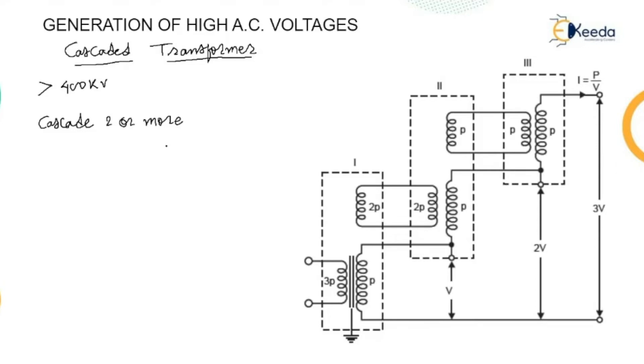The transportation cost and erection cost can be reduced, making transportation and erection easier. The transformer cost can also be reduced. Heavy insulation is required in a single-stage transformer for high voltages exceeding 345 kilovolt. It is found that the cost of insulation for such voltages for a single unit becomes proportional to the square of the operating voltage — this relationship is very important.